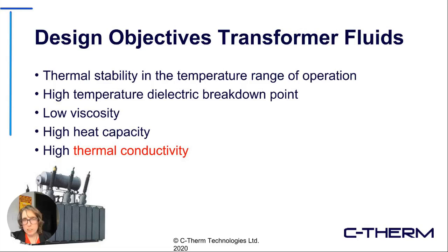When looking at transformer fluids, the goal is to design a material that exhibits thermal stability across the desired temperature range of operation. It should also have a high temperature dielectric breakdown point, so it doesn't easily overheat and have its dielectric behavior break down. We don't want shorts if it gets a little warm; we want it to keep performing well as a dielectric at the desired operating temperature and quite a ways above.